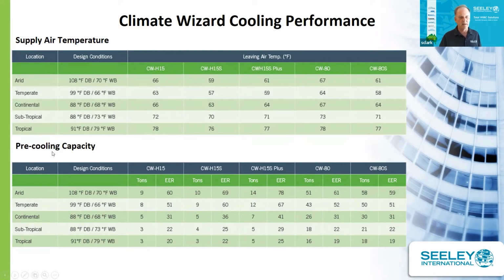And then if we come down here and look at the pre-cooling capacity for these same climate zones, we look at the tonnage, notice the EERs. I mean, these are orders of magnitude above conventional DX cooling. And that's because we have the efficiencies; our units use very little energy since there are no compressors in the units.